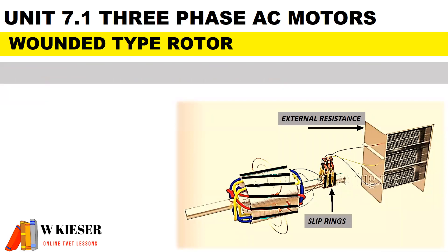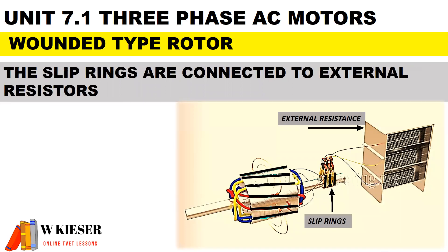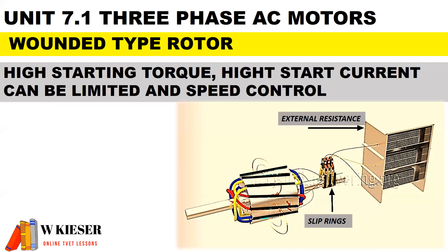For the wound type rotor, also known as the slip ring rotor, the rotor windings are connected in star to the slip rings. The slip rings are connected to external resistors, which allow for variable speed control. It is mainly used in cranes and elevators. In terms of the advantages, it has high starting torque, high starting current can be limited, and we have variable speed control thanks to the external resistors connected to the slip rings.